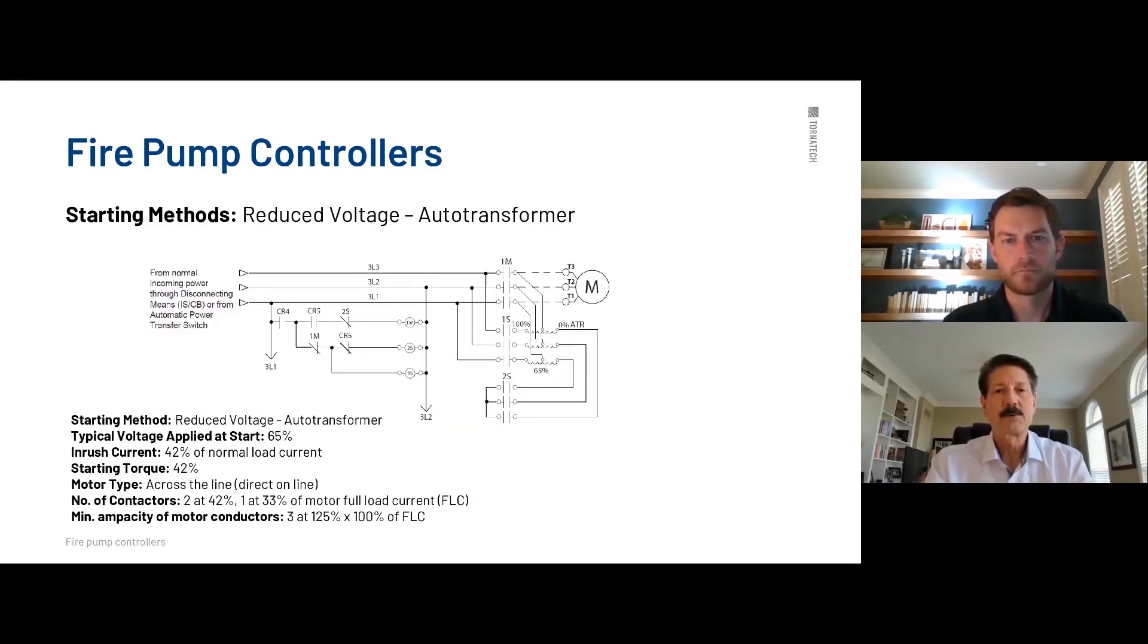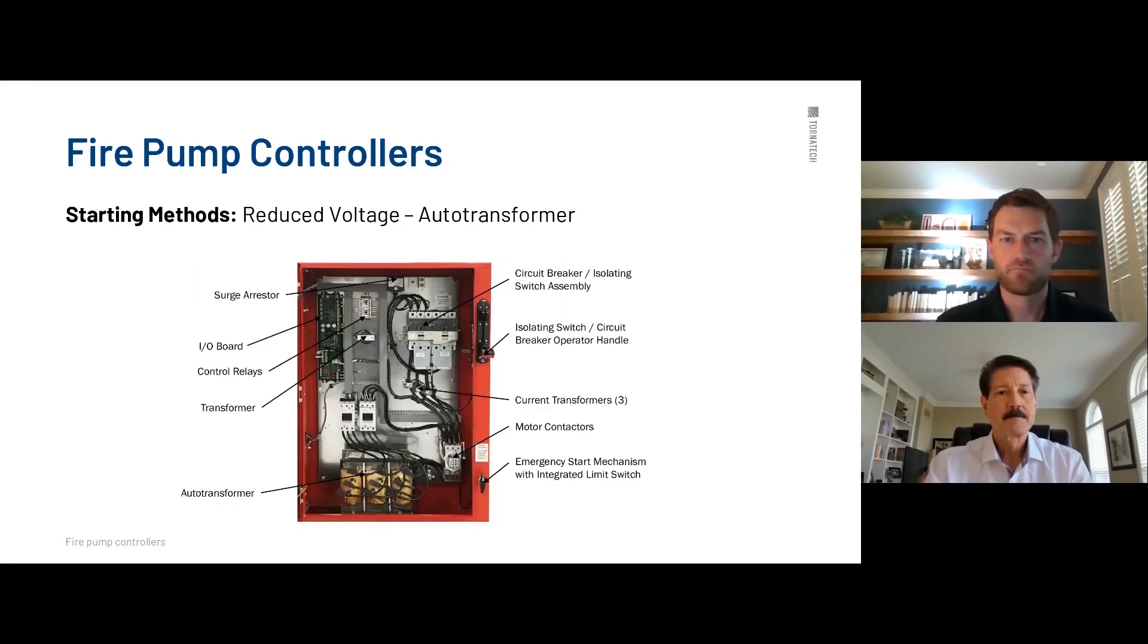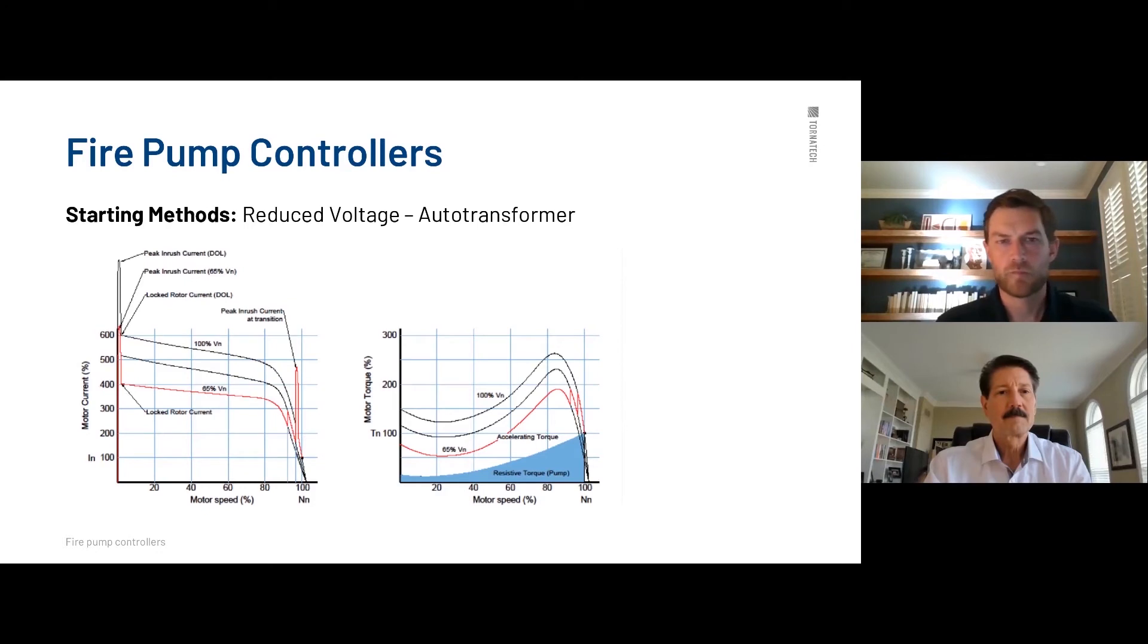Auto transformer, very brief. Again, we have a couple sets of contactors. We have taps off this transformer right here, typically 65%. There could be other adjustments factory set, but 65 is industry standard. And again, we're starting off at a reduced voltage, which is going to reduce current. And then as we ramp up, what will happen is, as you'll see briefly here, we have an inrush close to peaking three to four times full load amperage. Again, this high inrush here is almost negligible, the peak inrush.